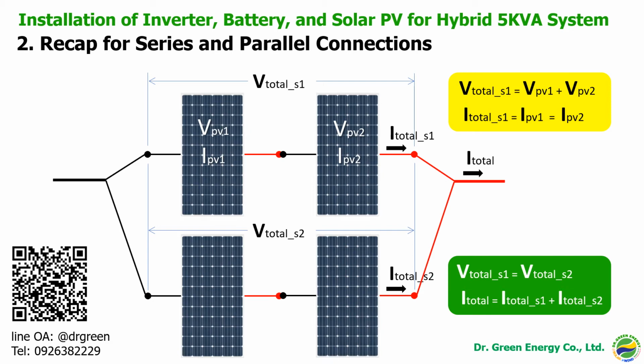However, the current output will be a summation. The total current output equals the current from string number 1 plus the current output of string number 2. If you connect more than two strings, you sum the current of every string together to get the total current output, which must be less than 50 amperes.